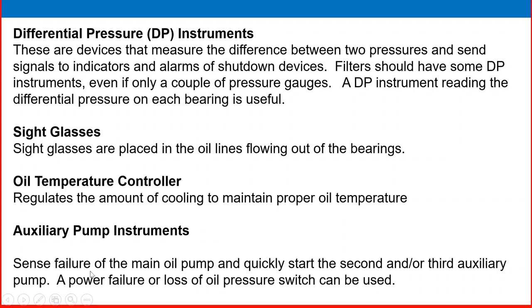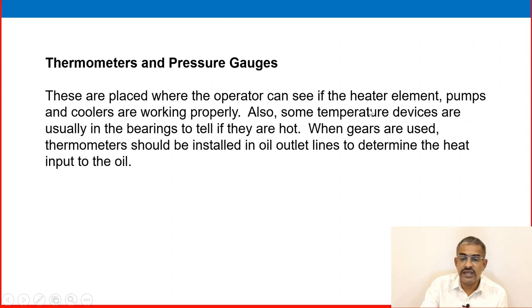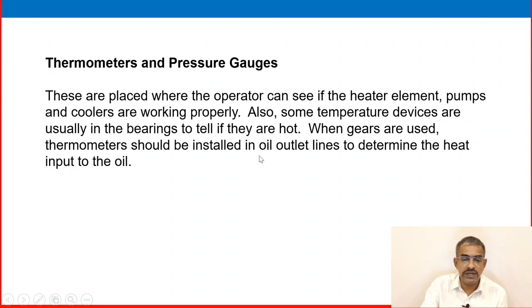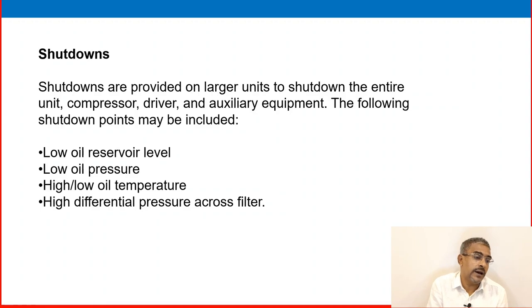An oil temperature controller is included — if oil temperature is too high, it may trigger a compressor shutdown. Auxiliary pumping instruments sense failure of the main oil pump and quickly start the second or third auxiliary pump using a power failure or loss of pressure switch. Thermometers and pressure gauges are placed where operators can monitor heater elements, pumps, and coolers. Temperature devices are usually installed in the bearings, and thermometers should be on gear oil outlets to determine heat input.